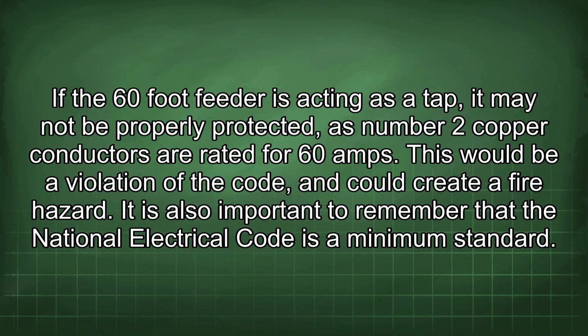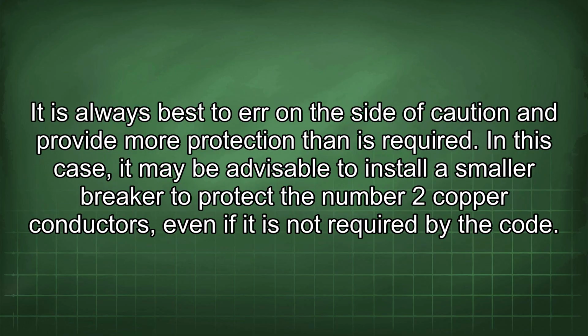It is also important to remember that the National Electrical Code is a minimum standard. It is always best to err on the side of caution and provide more protection than is required. In this case, it may be advisable to install a smaller breaker to protect the number 2 copper conductors, even if it is not required by the code.